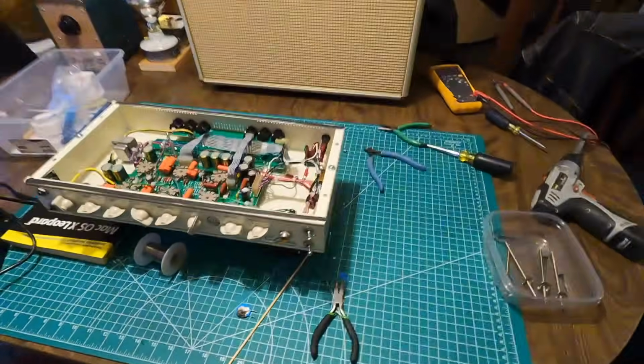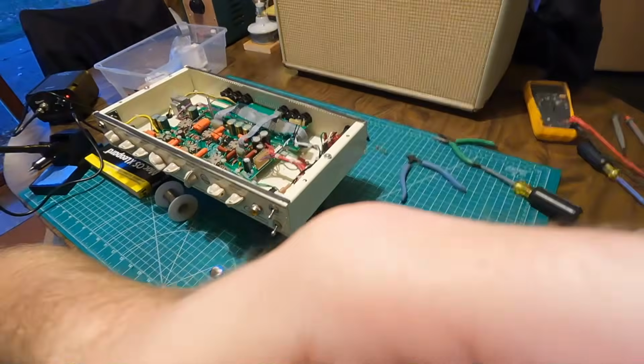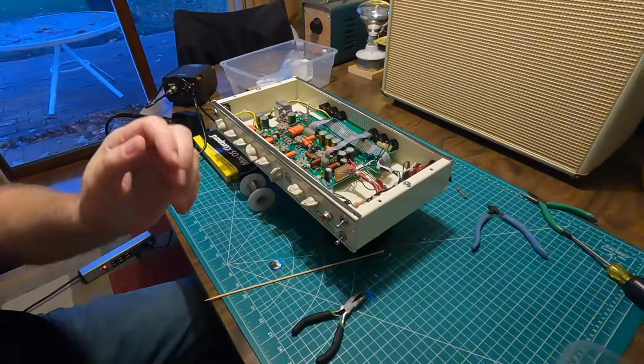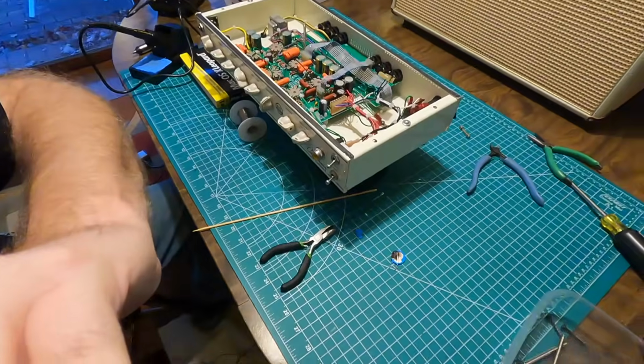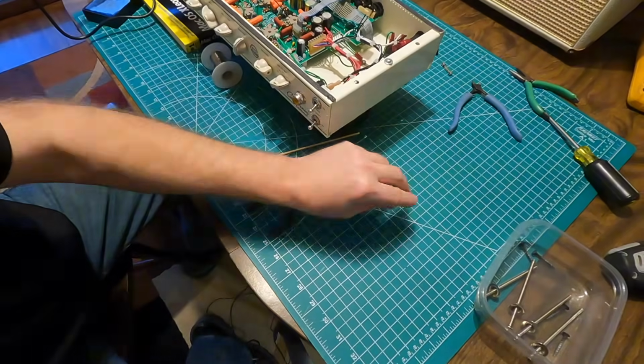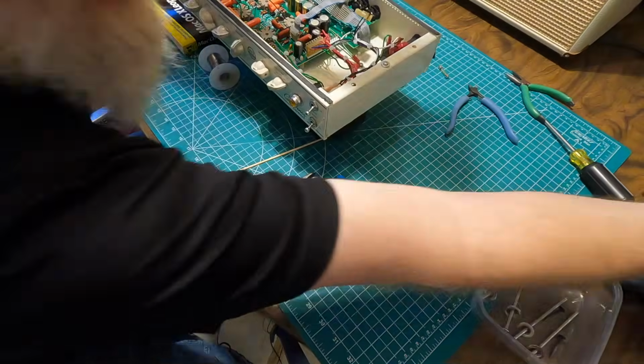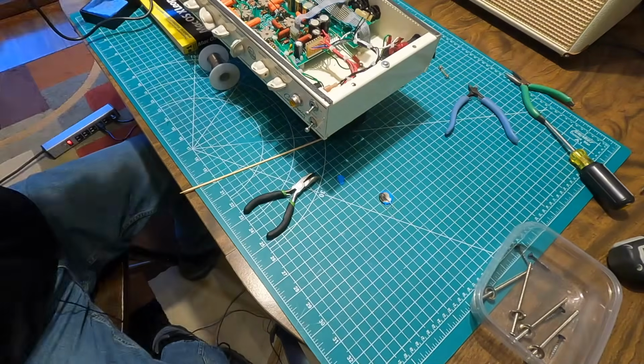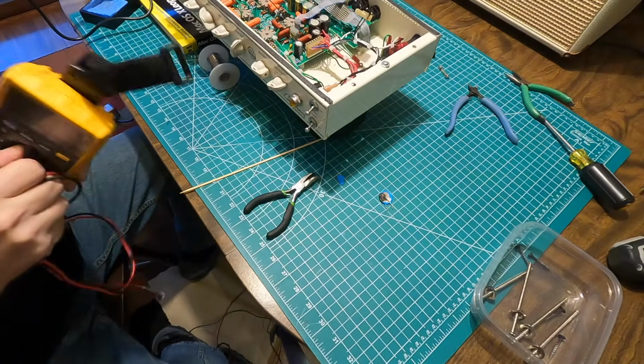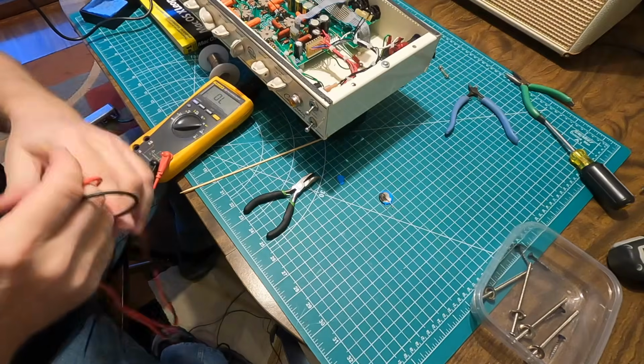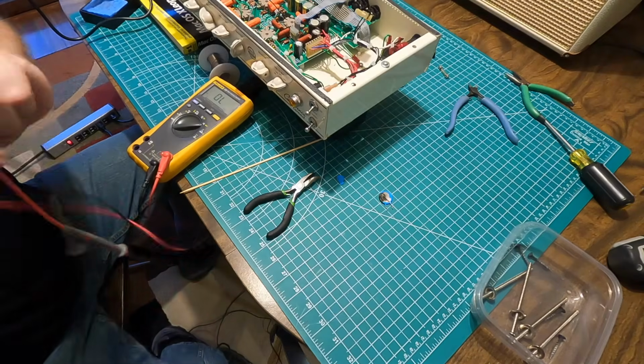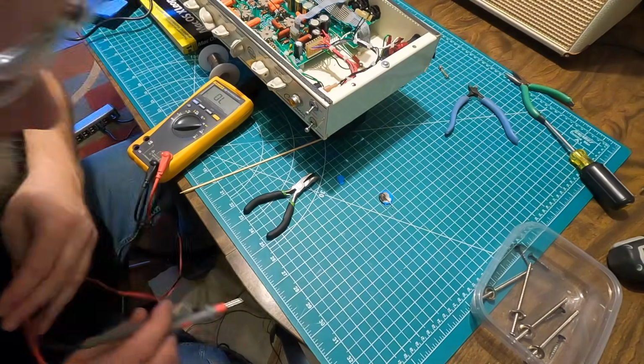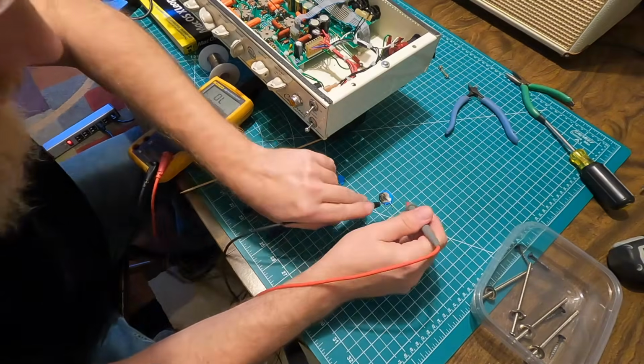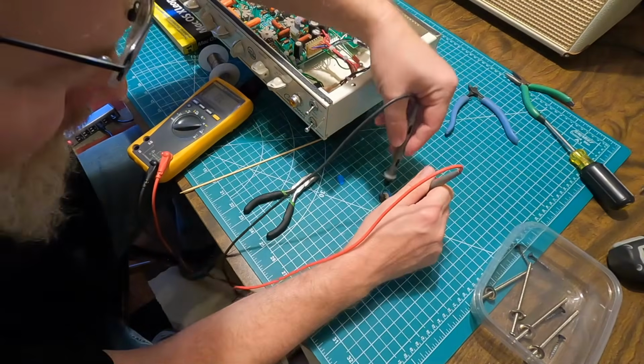But first, let's confirm that thing is wired straight across the AC. Can you see this? Yeah. Let's see if it's conductive. It should not be - MOVs are metal oxide varistors. The impedance should be very high until the voltage gets high, and then they dead short to blow the fuse.